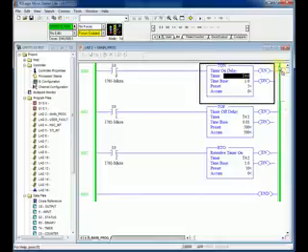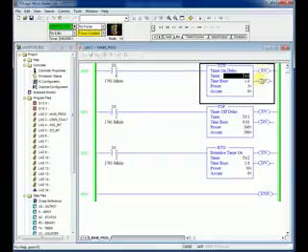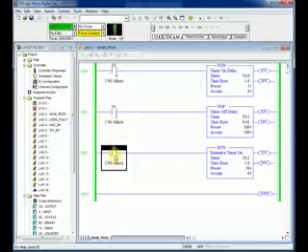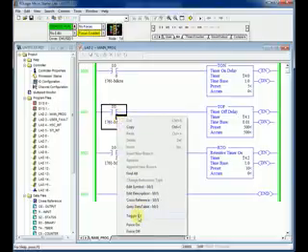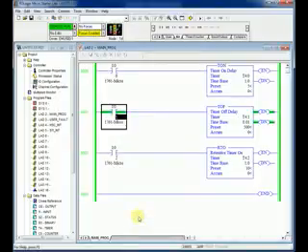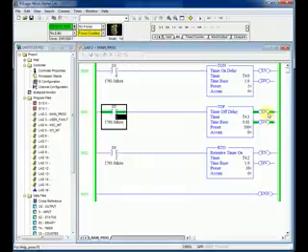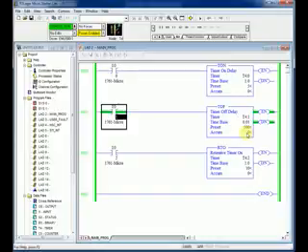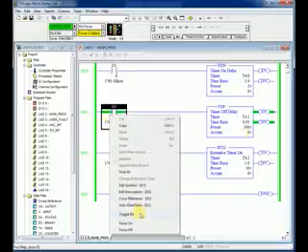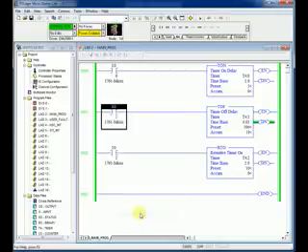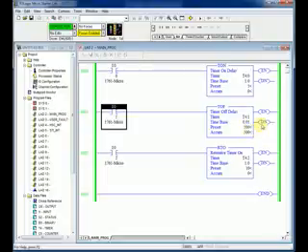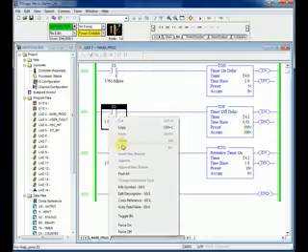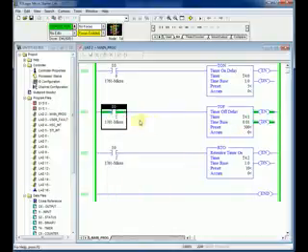Let's see timer off delay. What I said into timer off delay - if you will put it on, it will show you a done bit and also enable, but it will not start counting. It will start counting when you are putting on to off input. I put it on to off and it's counting milliseconds. As per the time base, 500 equals to 500, you can see the done bit is off. Let's see again. Done bit is on. Now watch the accumulator. When I turn it off, after 5 seconds the done bit will be off. This is the work of timer off delay.